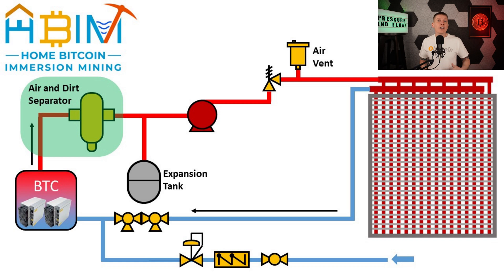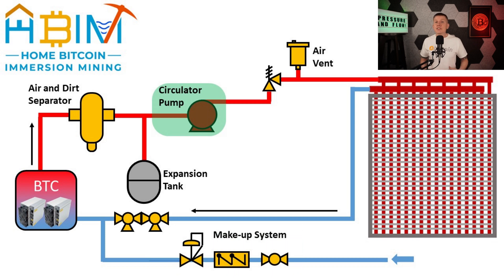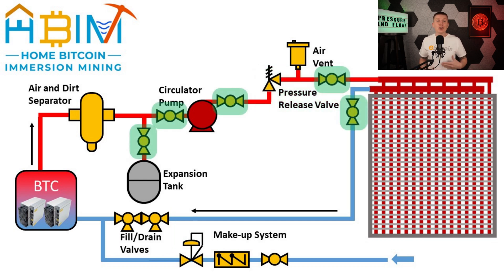With all that air leaving the cooling loop, fluid must be added back in to keep the system pressurized, so a makeup system must be added to ensure the loop always stays filled and maintains system pressure. Next, to move the fluid through the loop, we need a circulator pump. And finally, the system needs a few valves: filling and draining valves to fill and drain the system, a pressure release valve to protect the system in case of overpressurization, and additional valves to close off parts of the system for servicing or controlling where the heat flows to different parts of the house.